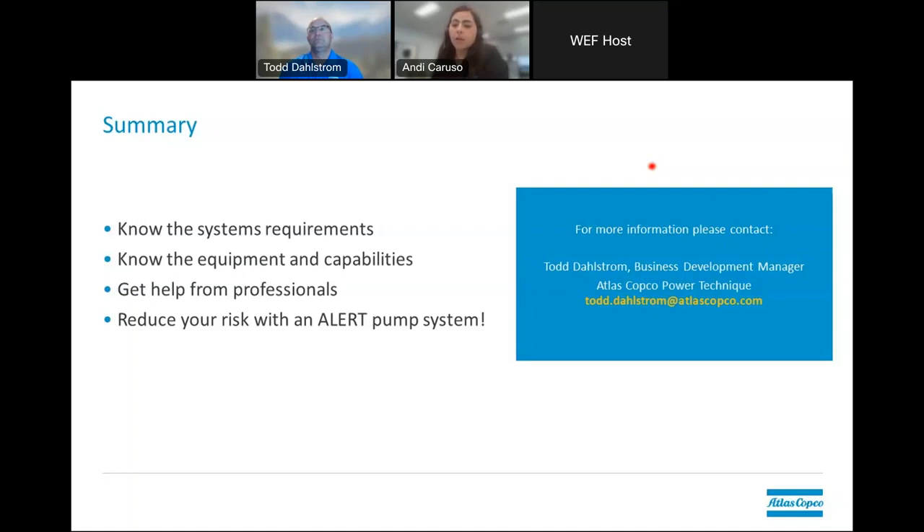Another question from Reza: Any limitation with the max capacity of the ALERT system? There are always limitations — you might have to use multiple units to hit a certain flow rate, or if there is an extreme amount of head, it may be outside the realm of capabilities. You do run into certain geographical areas where sewer systems run much deeper, and in those cases you are limited to submersibles because of the suction lift limitations of a centrifugal diesel trash pump. So it's not a one-size-fits-all solution, and there are capacity limits to these ALERT systems as there are with any system.